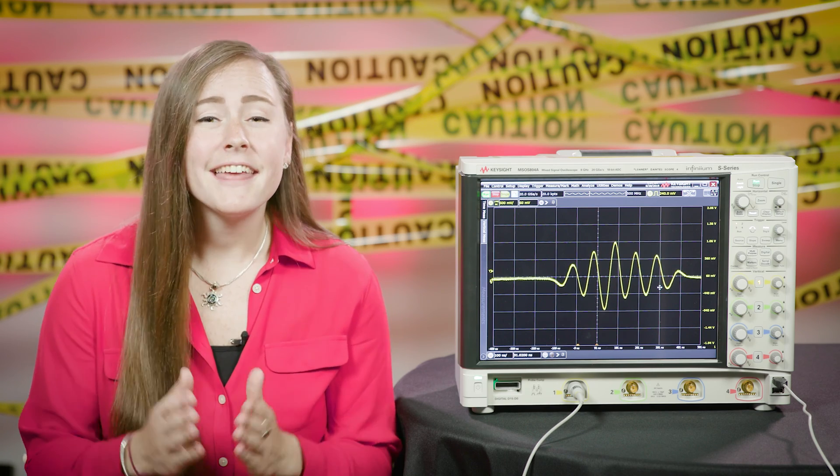However, there are many cases where this interleaving is implemented correctly, like with the Keysight S-Series oscilloscope we're using today. Interleaving isn't something to be afraid of, just something to be cautious of. There are also some extremely precise oscilloscopes out there, like the Keysight UXR series, that can reach incredibly high sample rates without interleaving ADCs. This will, of course, give you even more accuracy and higher signal integrity.